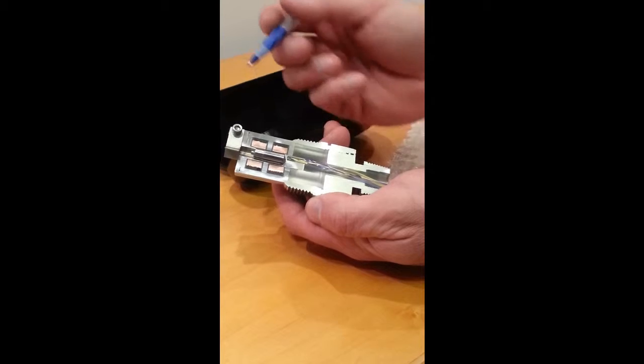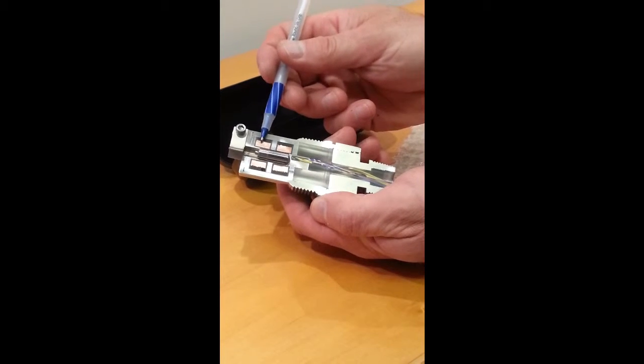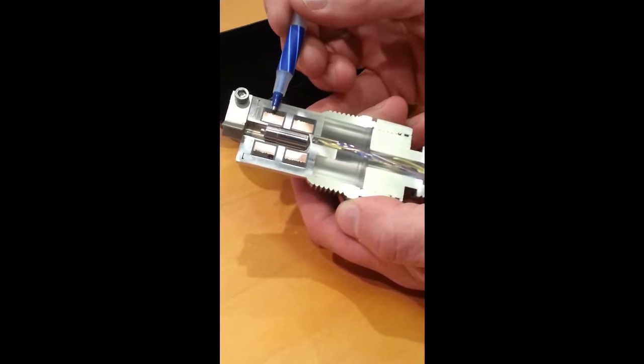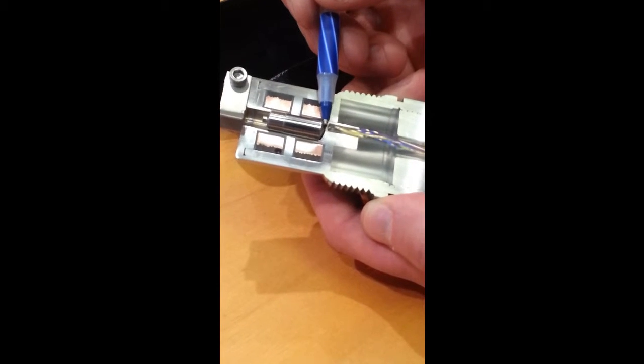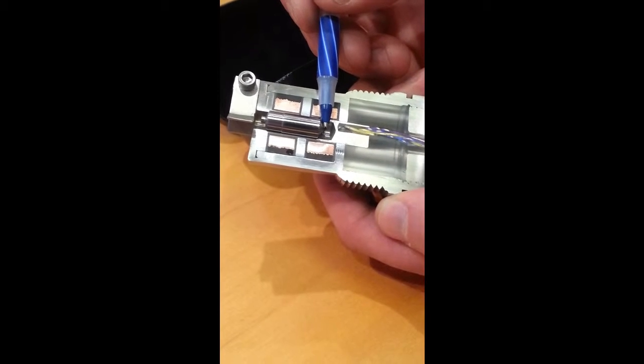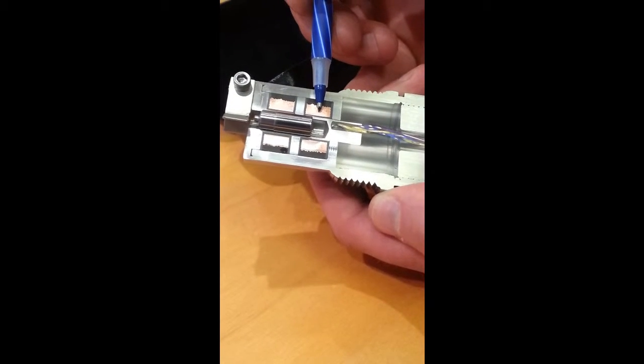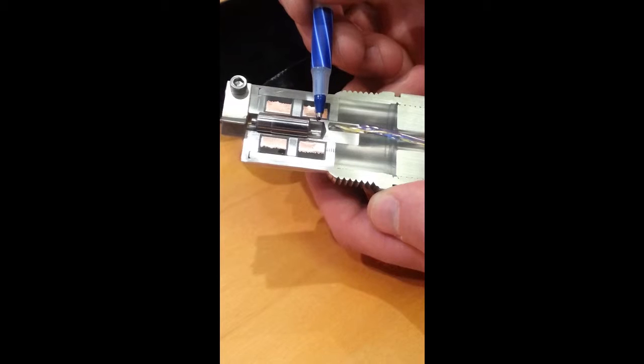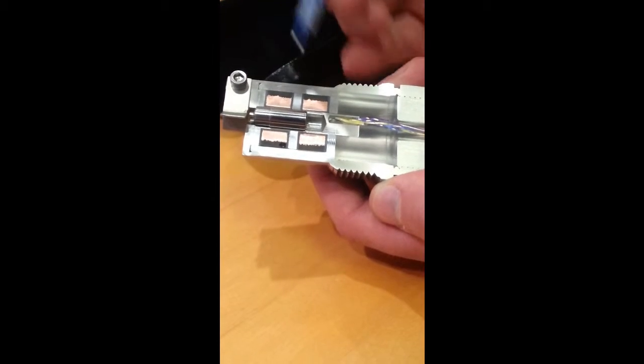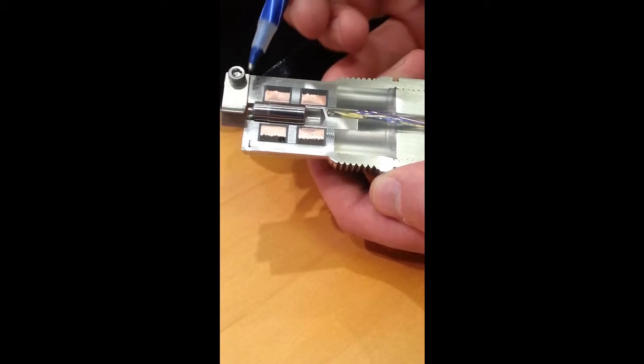I'd like to show you how it works. We have these two electromagnetic coils here inside the sensor. We energize the top coil. That pulls this piston up with magnetic force at a constant force. And this bottom coil tracks its position. Once it reaches an endpoint, the electronics now switch. This coil becomes active and this one tracks.